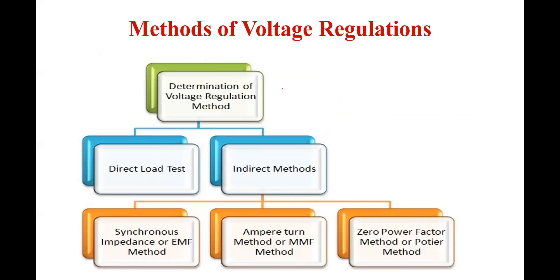The different classifications of voltage regulations: first is the direct loading test and second is the indirect loading test. The direct loading test is a conventional method — we directly connect a load to the alternator, then throw off the load and calculate load voltage and no-load voltage. This technique does not consider excitation and speed accurately, so it is only used for small alternators rated less than 5 kVA.